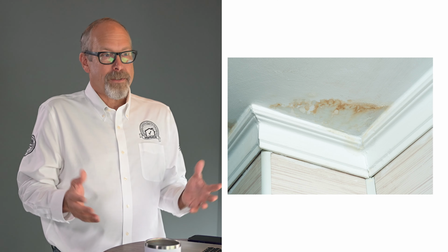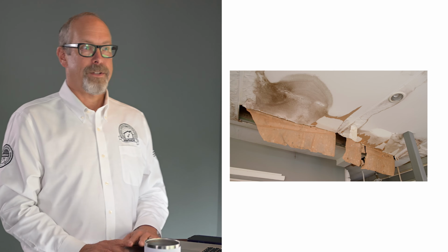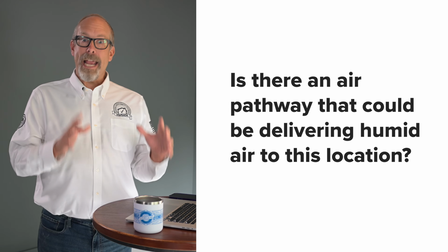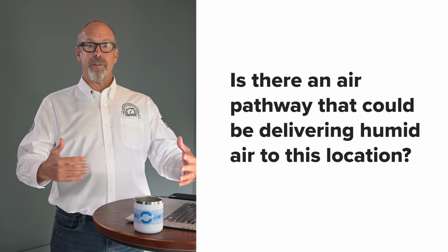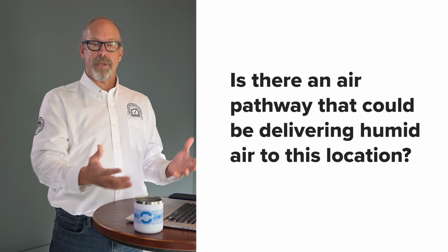So if you're looking around and you spot water stains, mold growth, deteriorated materials, you can work backwards to figure out the moisture source. Is there an air pathway that could be delivering humid air to this location? Is there a temperature difference that would cause condensation? Are there building assembly details that could trap moisture once it arrives?